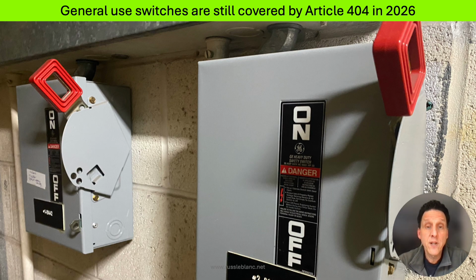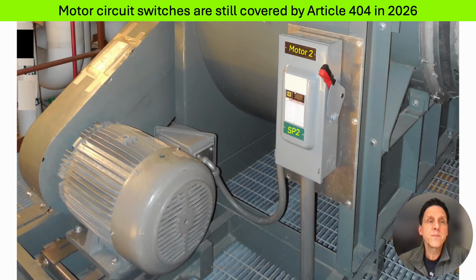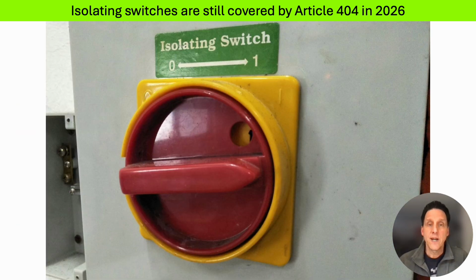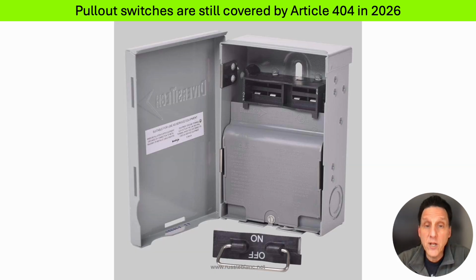So general use switches, like on the graphic here, will still be covered by Article 404 in 2026. And motor circuit switches are still going to be covered by Article 404 in 2026. Isolating switches are not intended to be opened under load, so you shut the power off somewhere else, like at a circuit breaker, for example, and then you can come and open up the isolating switch. Again, not under load, and now the power is disconnected and you can lock out and tag out the isolating switch. These are covered by 404 in both 2023 and in 2026. Pull-out switches, these are specifically mentioned now in 404. These will be covered by 404 for 2026.